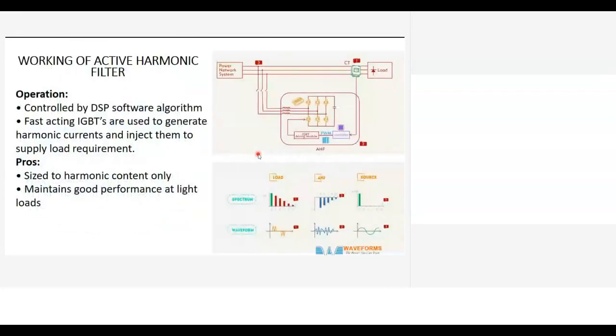So I was talking about the active filter using a technique called cancellation. They use a digital signal processor, software algorithms, and all that. What they have is a fast-acting IGBT. What it normally does is sense the harmonic generated in the network, and then it generates an equal and opposite pulse, equal to the harmonic generated in the network, and they inject that into the system. The cancellation happens this way.